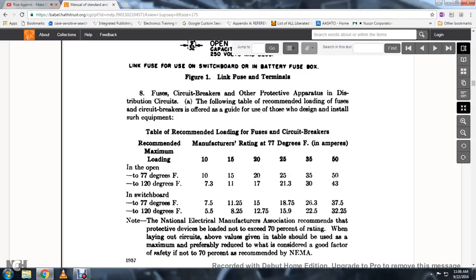Fuses and Circuit Breaker: The following table shows recommended loading of fuses and circuit breakers as a guide for those who design and install such equipment. The table shows recommended loading speeds with manufacturer rating at 77 degrees Fahrenheit: 10, 15, 20, 25, 35, and 50. Values for open, to 77 degrees and to 120 degrees, and switchboard 77 to 120 degrees are provided. The electrical manufacturers association recommends protective devices located not exceeding 70% of the rating when laying out circuits. The values in the table should be used as maximum, preferably reducing by what is considered a good safety factor, if not 70% of the recommended NEMA.